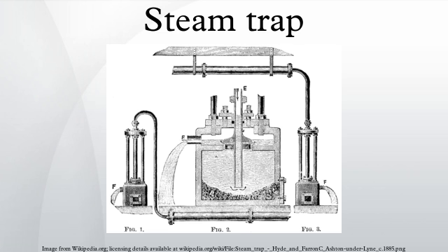Temperature traps have a valve that is driven on/off the seat by either expansion/contraction caused by temperature. They differ from mechanical traps in that their design requires them to hold back some condensate, waiting for it to cool sufficiently to allow the valve to open. In most circumstances this is not desirable, as condensate needs to be removed as soon as it is formed. Thermostatic traps and bimetallic traps are examples of temperature-operated traps.